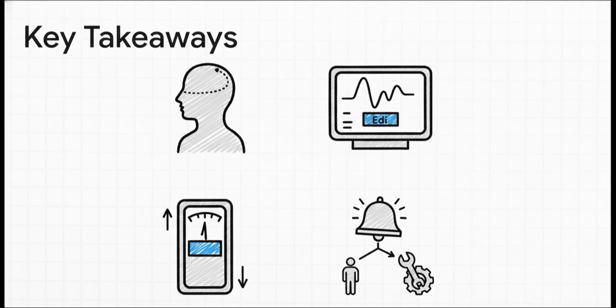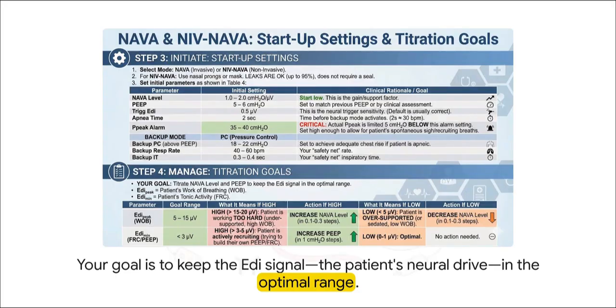So, to wrap it all up, let's boil it down to the key takeaways. First, that accurate NEX measurement is the foundation for everything that follows. Second, always use the on-screen ECG and Edi signals to be sure about your placement. Third, remember to constantly titrate your settings to keep that Edi signal in the optimal zone. And finally, learn to tell the difference between an alarm that signals a real patient need and one that's just a settings issue. Ultimately, it all comes back to this one thing.